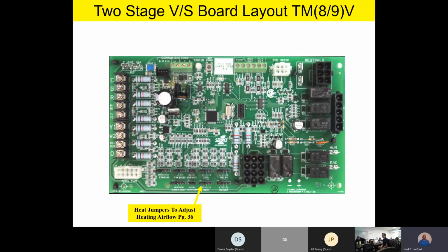Now, please remember, if you pull your service panels off the furnace, you're going to notice a data plate. Always make sure and set up or tweak your heating airflow so that it's just about in the middle of your temperature rise. Remember, team, to find temperature rise, you take your supply air temperature and your return air temperature and find the difference. So let's say we have 140 degree supply air temperature and 70 degree return air temperature. My temperature rise in that example would be 70 degrees. So look at your data plate, and you can tweak your airflow for heating by utilizing that heating airflow jumper down there.